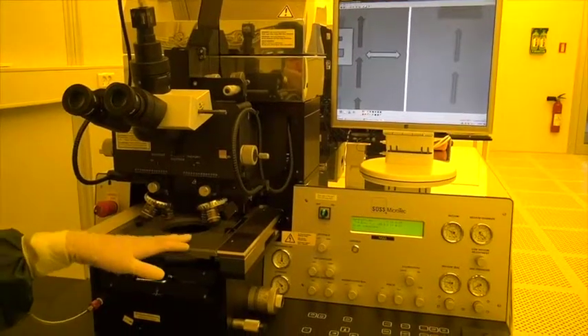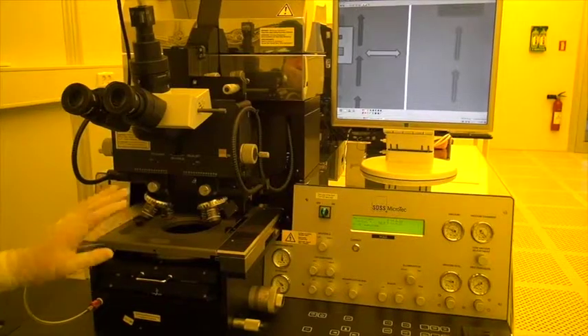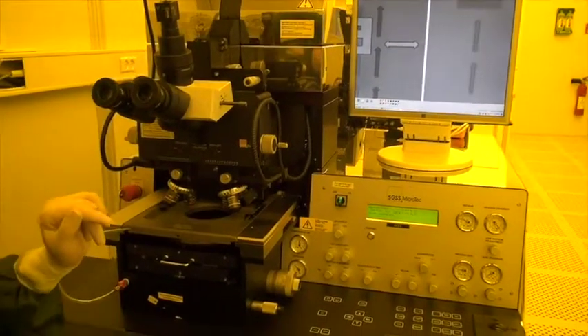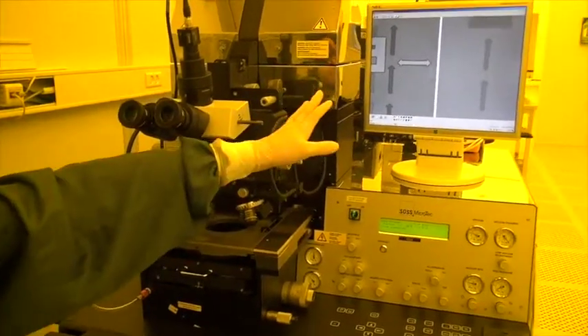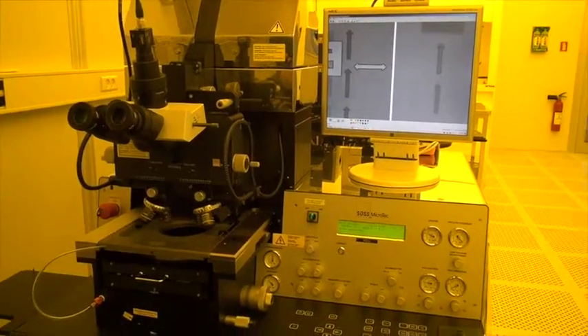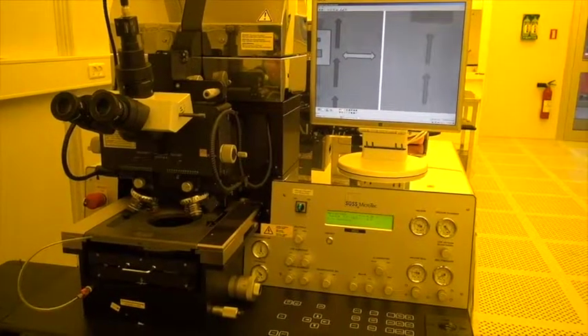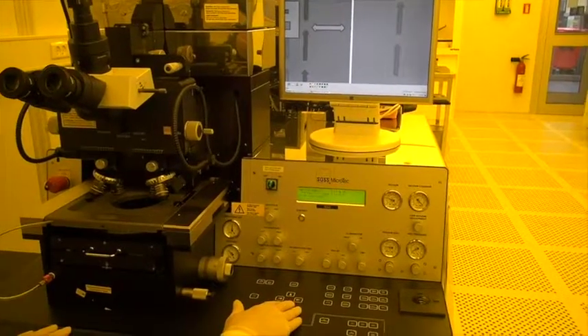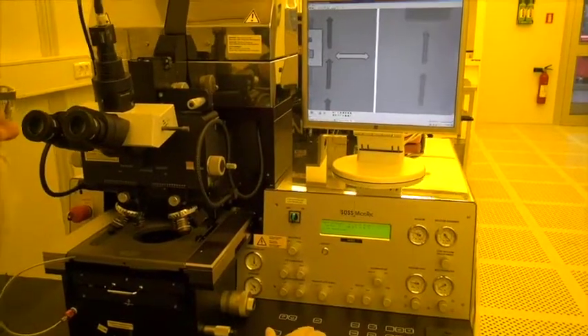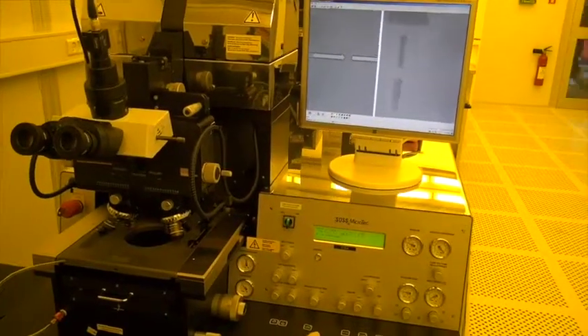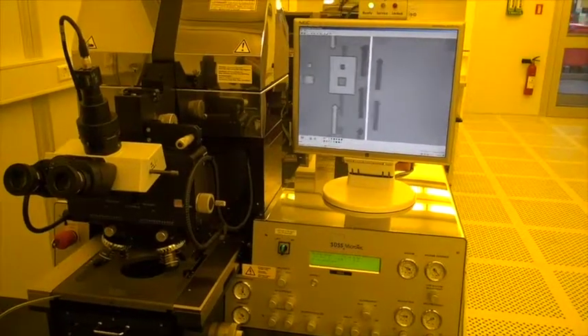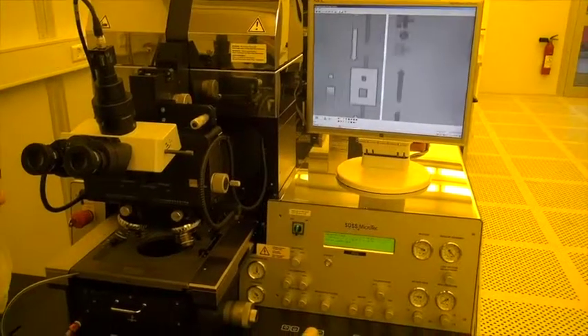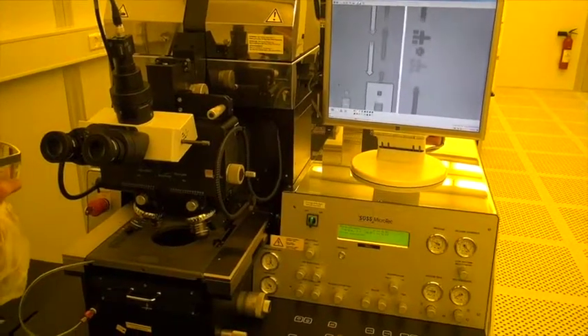And in this case, the microscope was nicely positioned in the center of the wafer. So I actually already see my alignment marks on the screen. But otherwise, I can use the X and Y buttons here to move the microscope around.